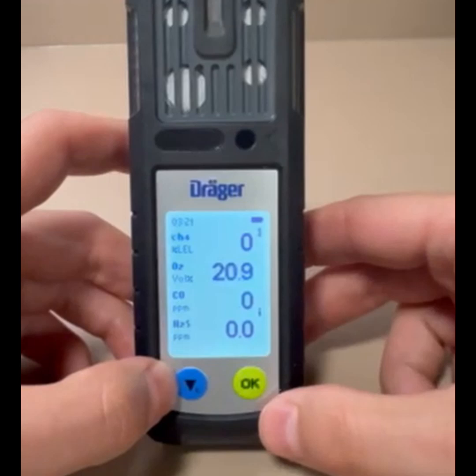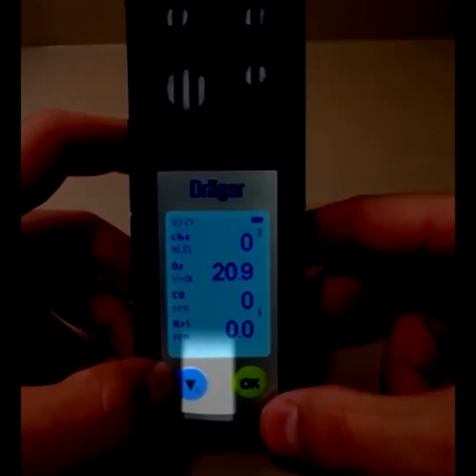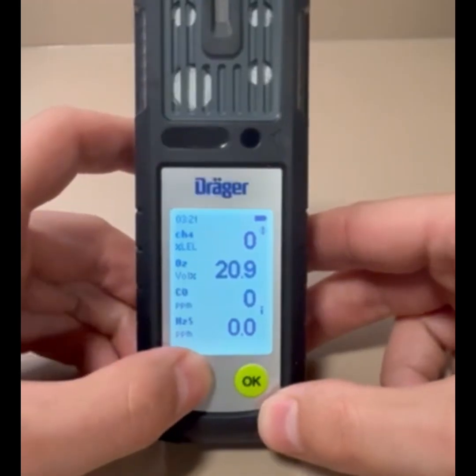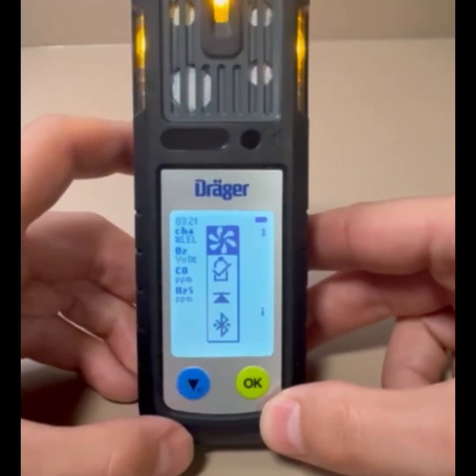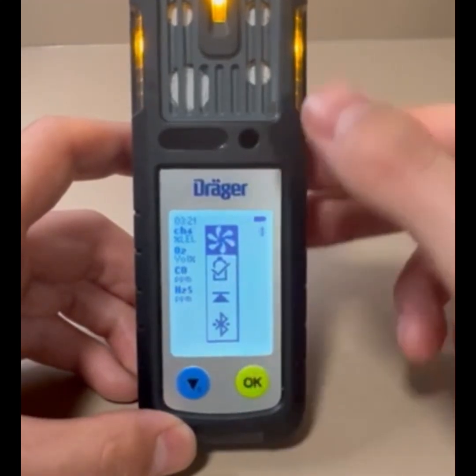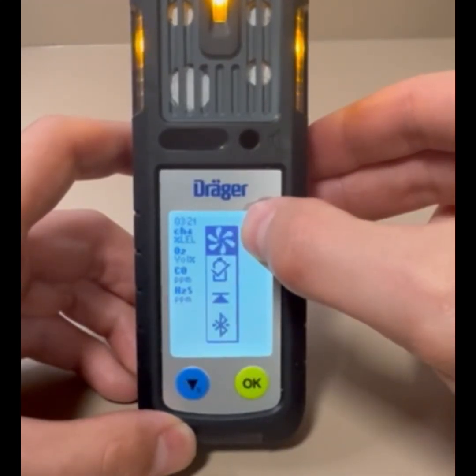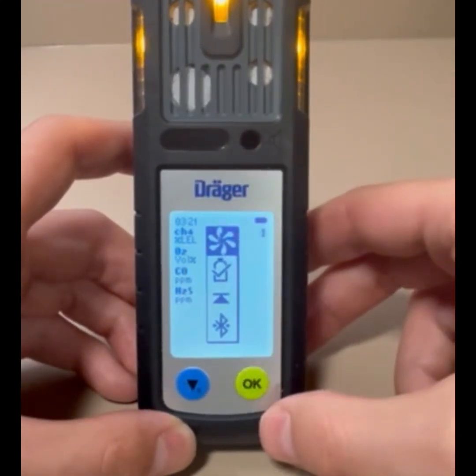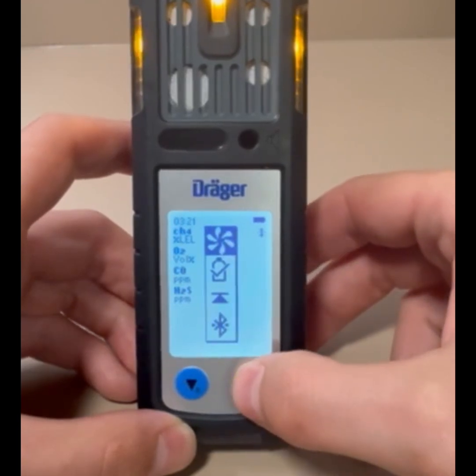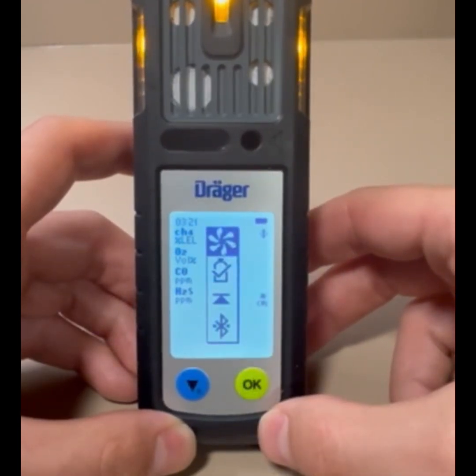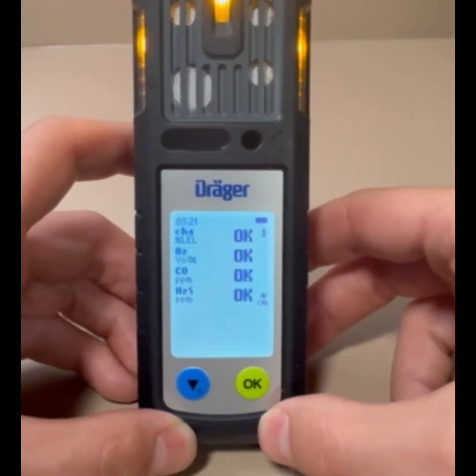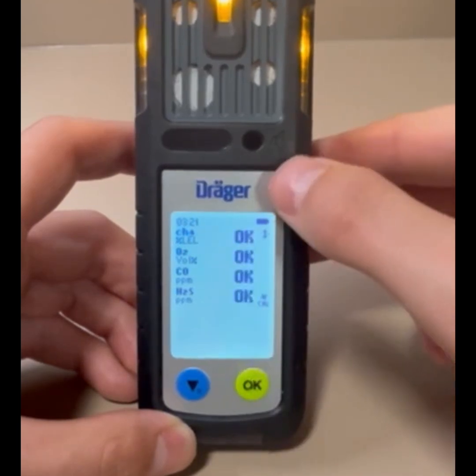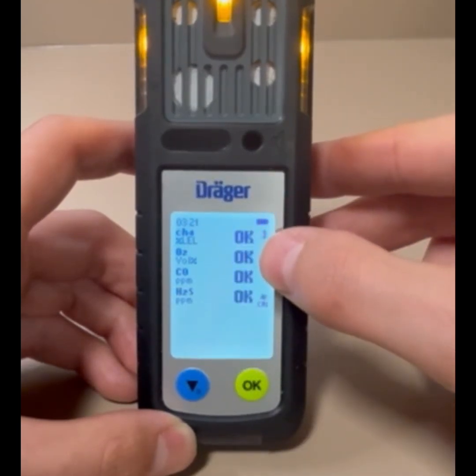To perform a fresh air calibration, press the blue menu button 3 times consecutively. From there, a menu screen will pop up displaying different functions. Make sure that the fan symbol is selected and press OK. After pressing OK, wait a few seconds. The sensors will then begin to flash. Make sure that all 4 sensors are displaying OK.